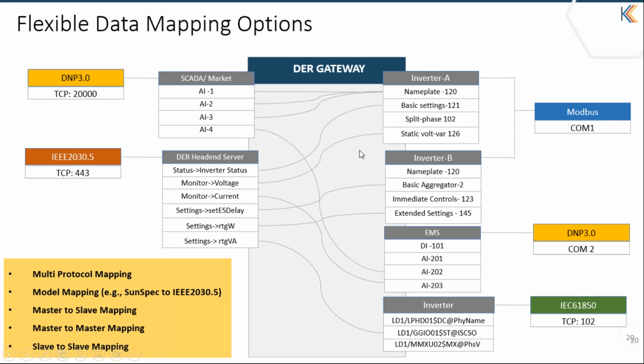Device model should be mapped to 2030.5 as well as to DNP3. It could be EMS systems or inverters or any other RTUs out there which can communicate on DNP3, and you should be able to pick up the data from these devices on DNP3 and map it to a northbound communication interface. Similarly, there could be devices with IEC 61850, and the logical nodes and logical device stacks have to be mapped to 2030.5 or DNP3.